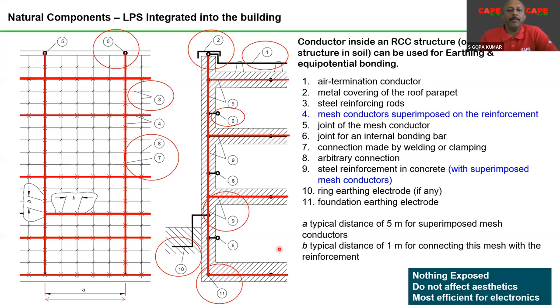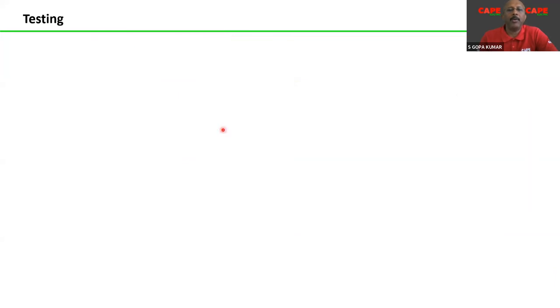Now, in this particular case, the down conductors and the earth electrodes or the foundation earthing are not exposed. They do not affect the aesthetics of the building, and it is most efficient for electronics, because what happens, you know, whenever there is a current flow through the structure, the current is split into several hundreds of routes. As a result, concentration of current through one specific conductor is less, because the current is going to flow through the entire building. As a result, the effect of the current flow with a large di/dt, rate of change of current, is reduced, and you get maximum protection for your electronics.